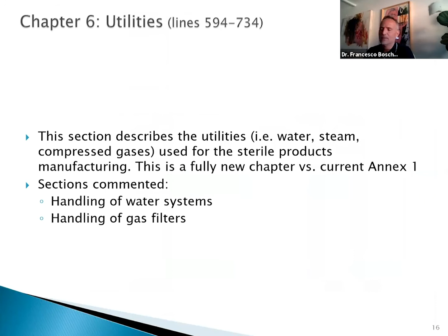Let's move now to chapter 6. As I was mentioning before, this is a brand new chapter, and the comments were about the handling of the water system and the handling of gas filters. One comment was that after disinfection and regeneration of the water system, monitoring, of course, should take place, and the results, according to the annex, should be approved before the water system is returned to use. But for the traditional microbiological method, this would imply waiting for more than 5 days. So we think as a team that this requirement may be excessive, especially for a qualified and well-known system.